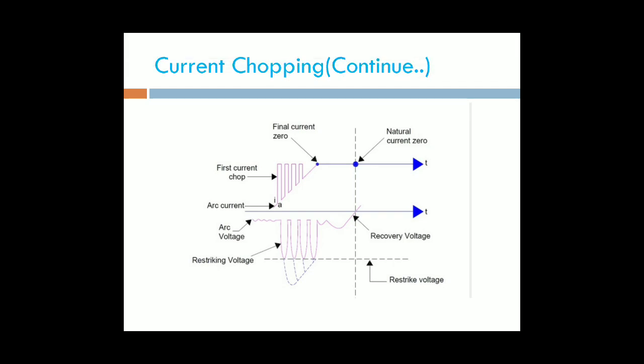This is the first current chopping and this is the final current chopping. This is the natural current 0. Before obtaining the natural current 0, the current is forcefully brought to 0. It is known as current chopping. This is the arc current. Next one is the arc voltage. This is the restriking voltage. At the end of the oscillation, we have the recovery voltage.